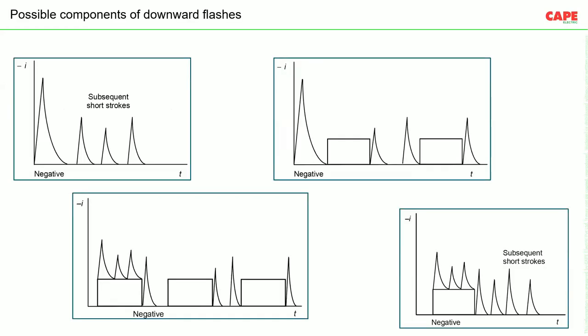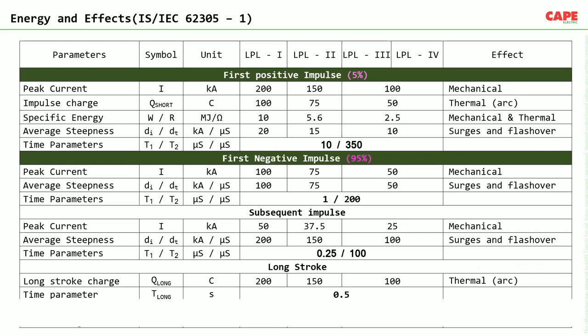Now, lightning impulse can come in various ways. These are a few examples of how a lightning impulse can come. For example, first one can be a long impulse followed by subsequent short impulses. The second one can be a very high impulse, followed by a long duration impulse, then a subsequent impulse. Another possibility is a long duration impulse with superimposed short duration subsequent impulses. It can be anything, like multiple long duration impulses also. So here we have defined some parameters of how these impulses will react.